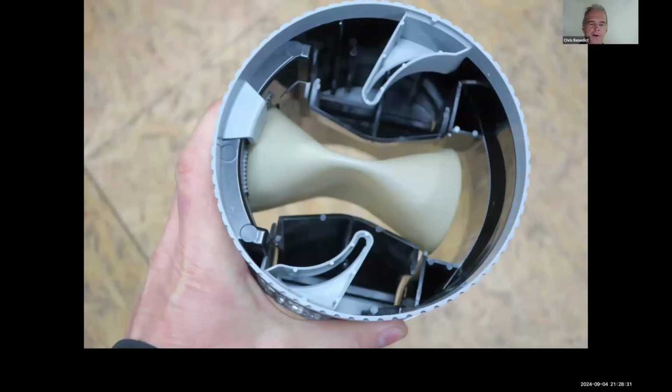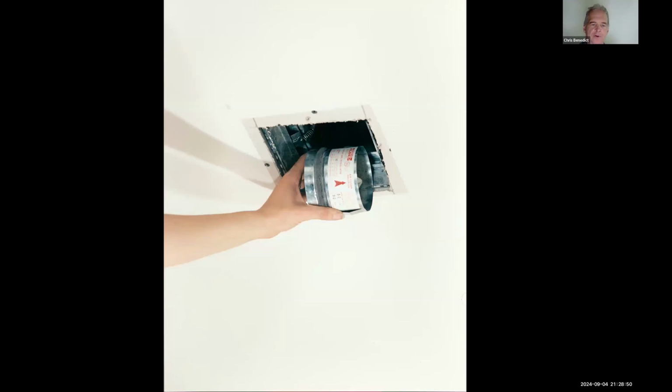That's the airflow regulator. You set it for 20 CFM or 50 or whatever. You move that sliding piece at the left, and the balloon-looking thing blows up in response to pressure drop across the device, and it limits the airflow to whatever you set it for. So you can have the bathroom get this much, the kitchen get that much, etc. It gets inserted in that box like that.